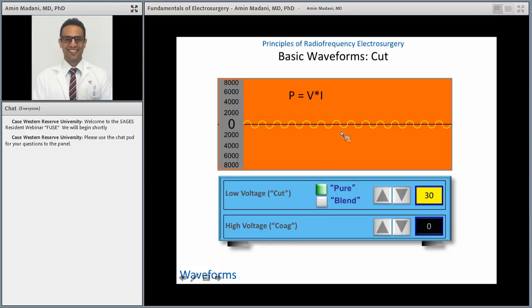Now, let's say we ask them to put it on cut 100, so higher power. You're going to get the same waveform, so 100% duty cycle. So 100% of the time, current is going through the circuit, but more voltage, because you've increased the power. So you're going to have a higher amount of energy because of that. And if we go back to 30, we get the same waveform, but lower energy. So the cut waveform is continuous, and it's relatively low voltage.